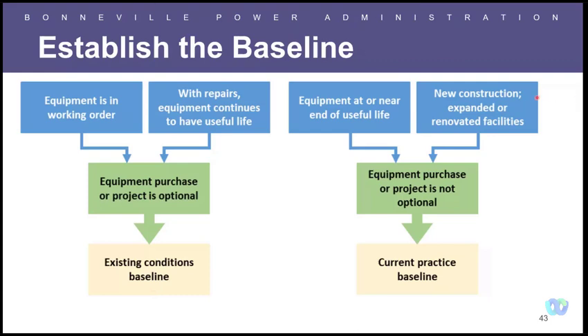But on the other hand, if you're doing new construction, or if your equipment is at the end of its useful life, if it's 25 years old, a piece of equipment, and it needs to be replaced, your equipment purchase, it's not really optional. This is a mandatory one-for-one, oftentimes, replacement. And using what's called either a code baseline or a current practice baseline is recommended in these circumstances. The current practice baseline is if there's not a code-specific item that applies, there's current industry practices. So a current practice is that that piece of equipment already comes with a VFD. You're not going to probably get credit for the VFD, as that should be considered part of the baseline.